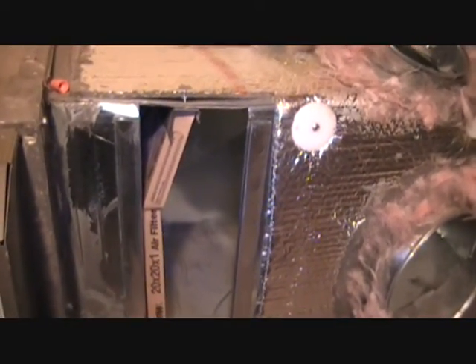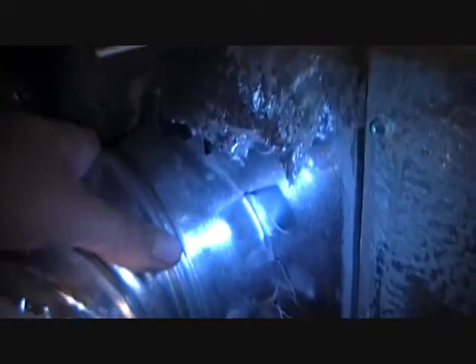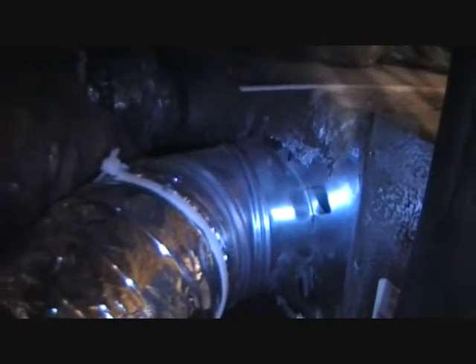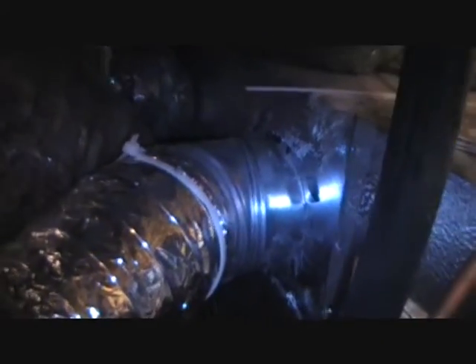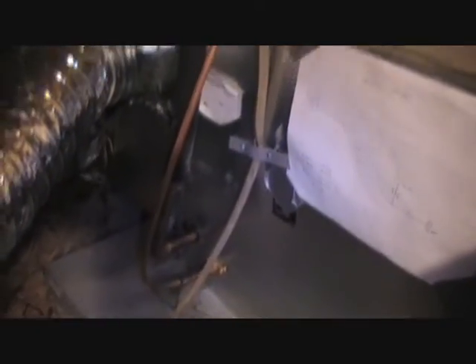The thing that's amazing to me is that they took the time to seal the ductwork. You can see the mastic around the takeoffs on this plenum. But on the supply, it's another story. These are huge, huge air leaks, and you can actually see the dust buildup that has worked its way through the system around where the air is leaking. That is a huge, huge energy loss. We don't have continuous insulation on the suction line. Now our area is pretty dry and that's not always a huge issue, but in the spirit of good workmanship, that just does not fly.